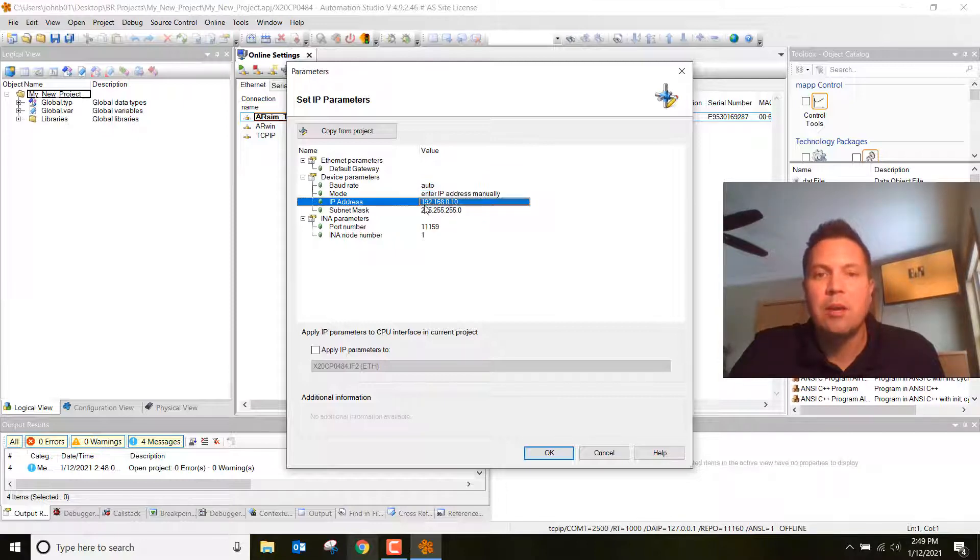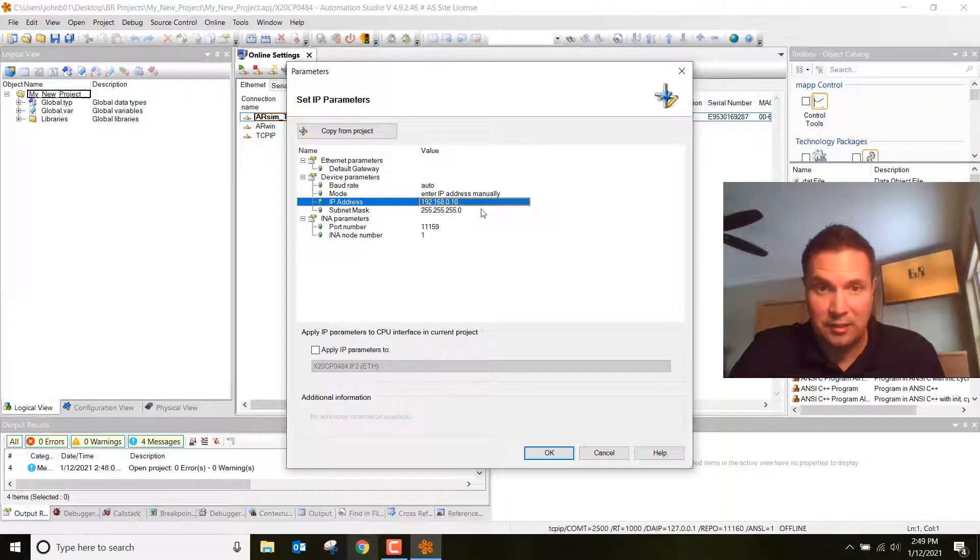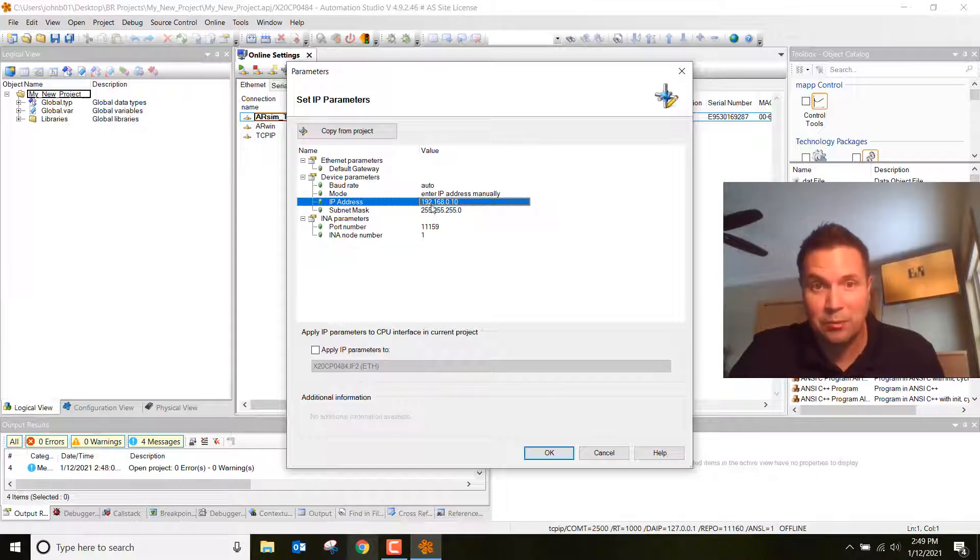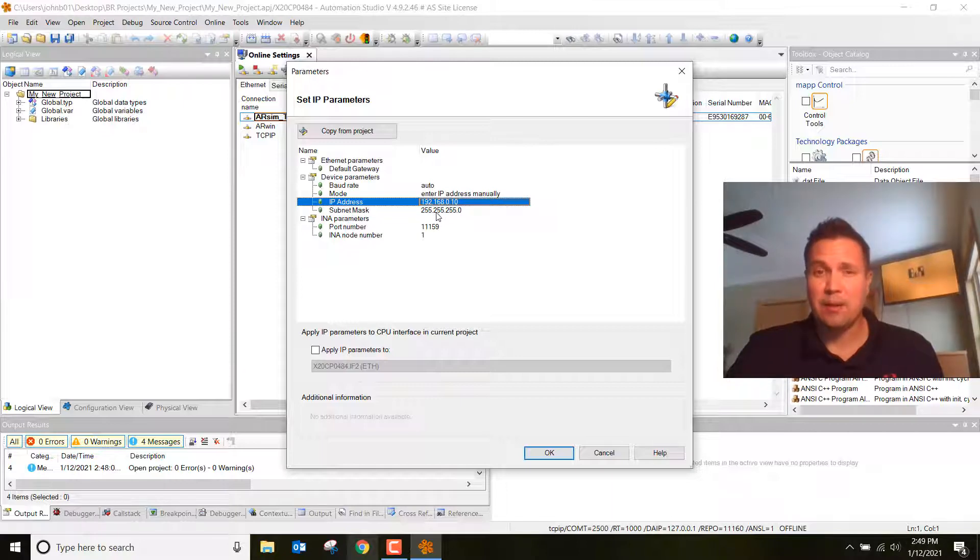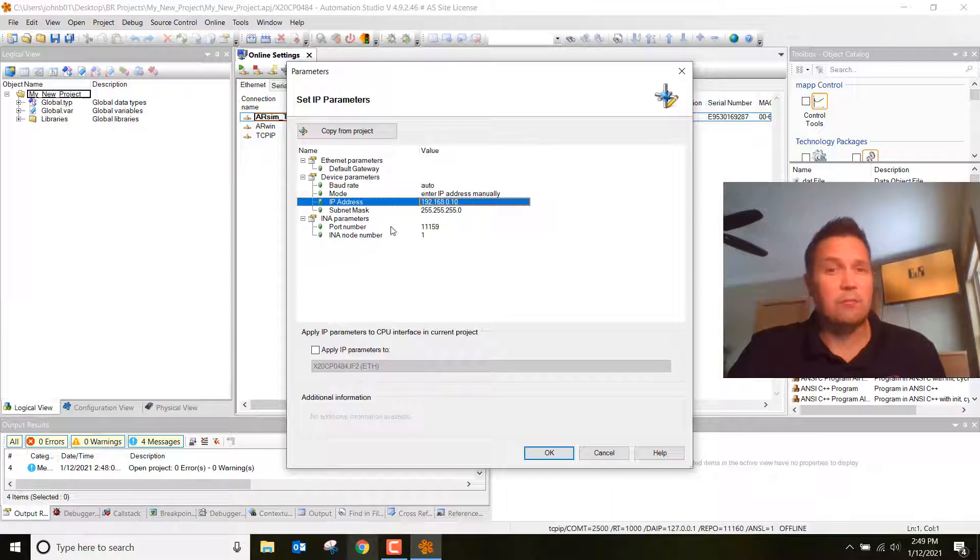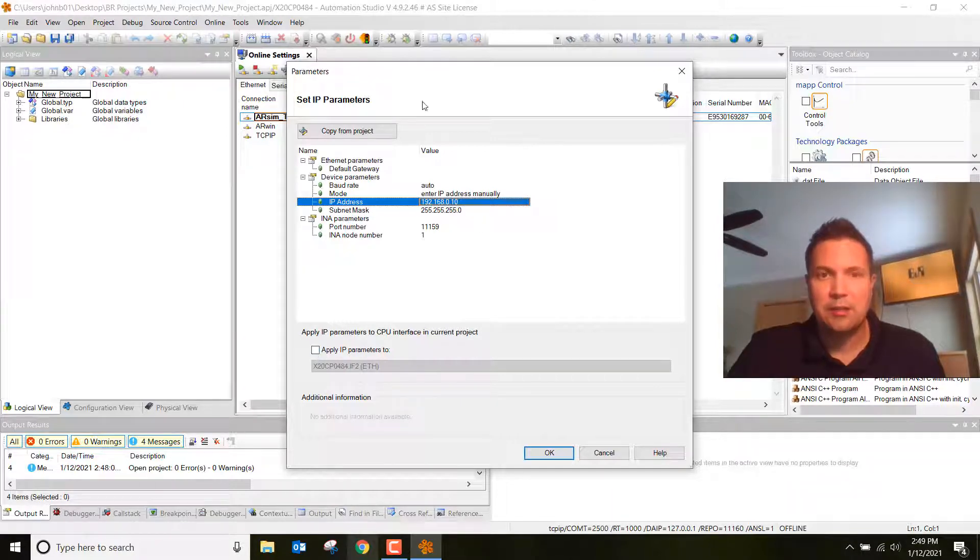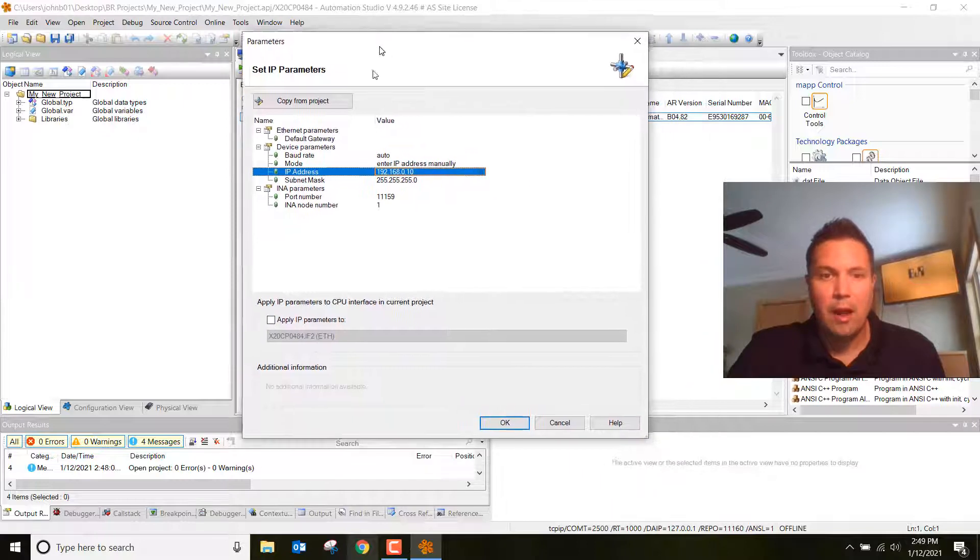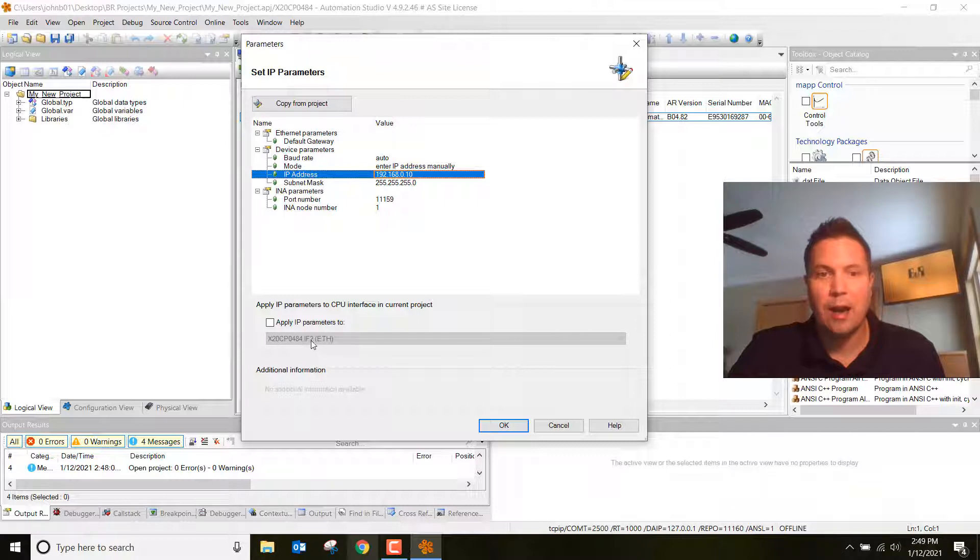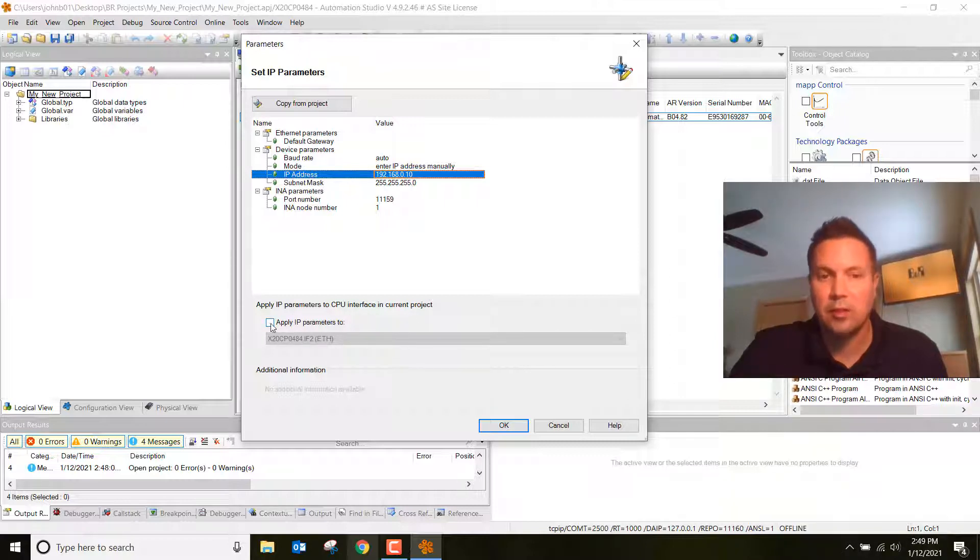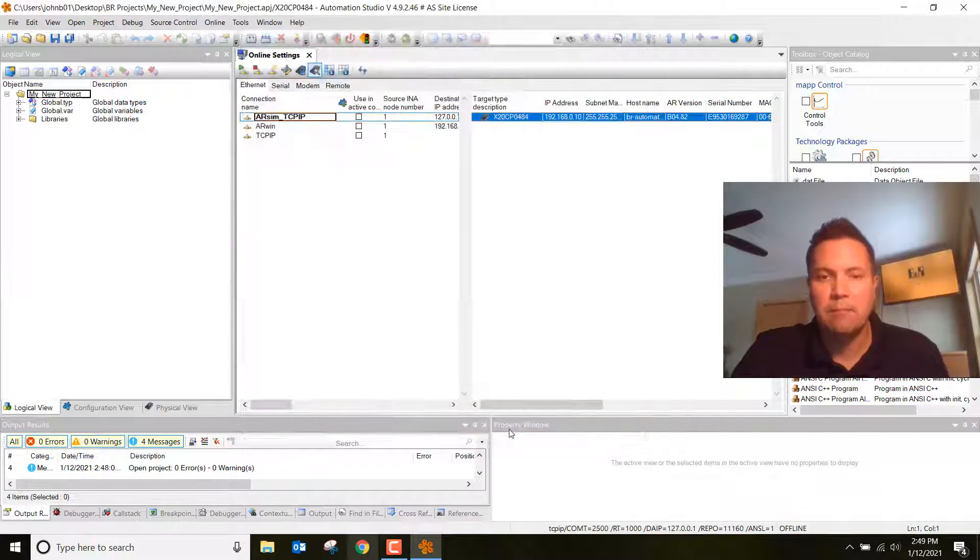Make sure you enter the IP address. It's the same as the IP address on your PC other than this last digit. So I have it set as 192.168.0.10. The subnet is 255.255.255.0, very similar except for that last digit. Make sure I check this box that says apply IP parameters to the X20CP0484 IF2 ethernet port. Check that box, it's very important. Go ahead and click OK.